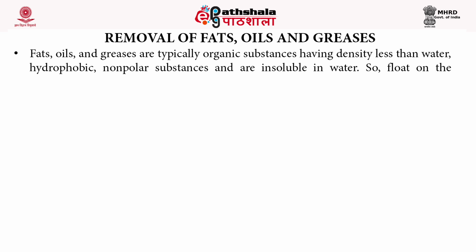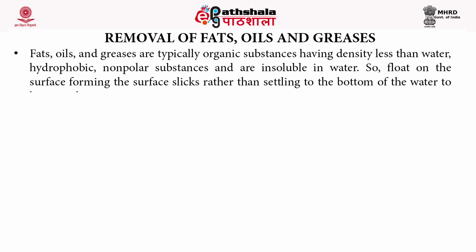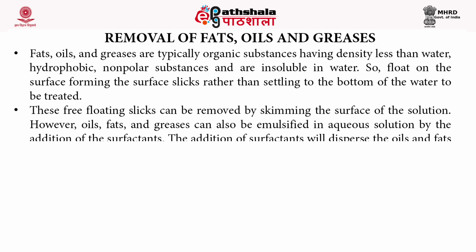For the removal of fats, oil and greases, which are organic substances having density less than water, they float on the surface forming surface slicks rather than settling to the bottom of the water. They behave in this way because they are hydrophobic, non-polar substances and insoluble in water. These free-floating slicks can be removed by skimming the surface of the solution.